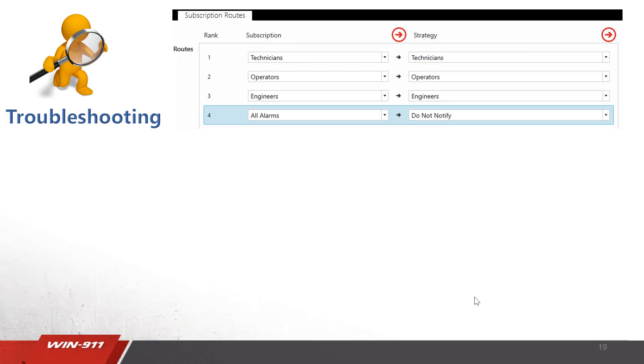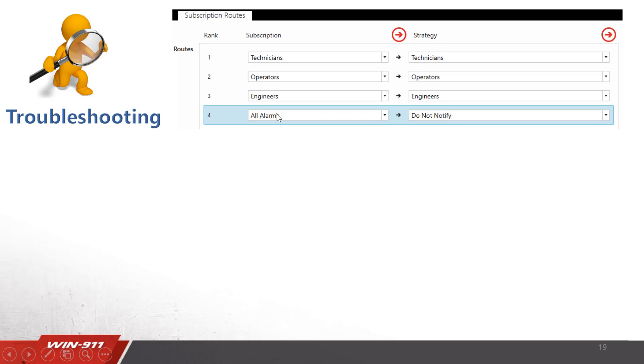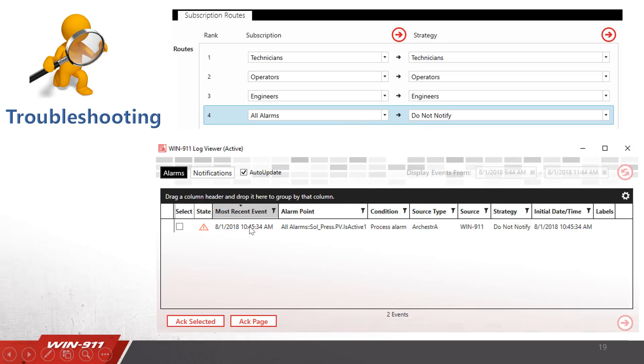Going back to the troubleshooting scenario — we added that 'do not notify' strategy. If an alarm filters through all subscription filters and is caught by the all alarms catch-all, that's a signal something is wrong. For example, if you didn't have the correct case sensitivity on your subscription filter — and note that items in WIN911 are case sensitive for subscription filters — or if you didn't have the right filtering criteria, your filter didn't catch the alarm. Using Log Viewer, we can see exactly the alarm that went off and that it went to 'do not notify'. That's an indicator to go back and reevaluate your subscriptions and make sure you're catching the right items.